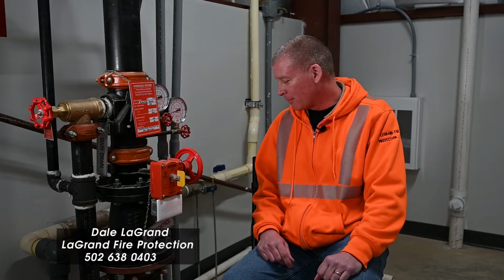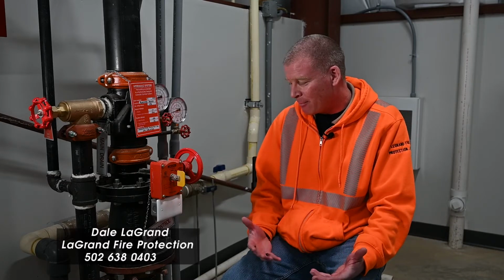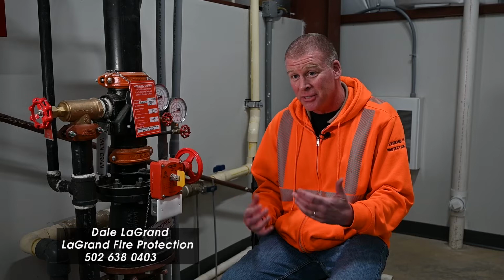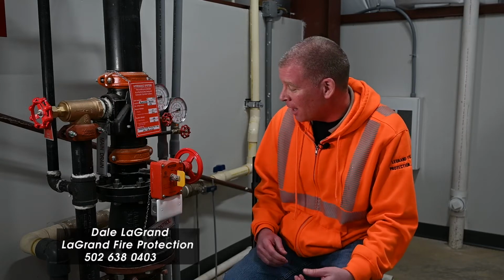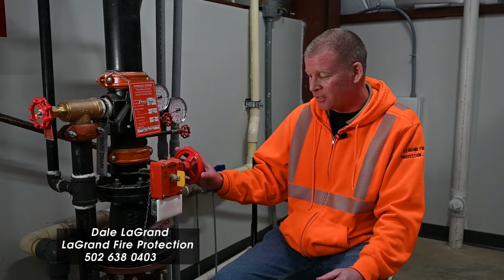Let's get started. I'm Dale LaGrand with LaGrand Fire Protection, and we're at Bluegrass Roller in Shelbyville, Kentucky, and this is the fire protection riser. I'm going to go through and explain what needs to happen if you have an accidental discharge of a sprinkler head. The first thing you want to do is shut this valve. This controls all the water that's coming to the building.